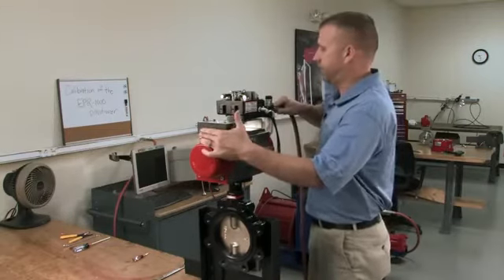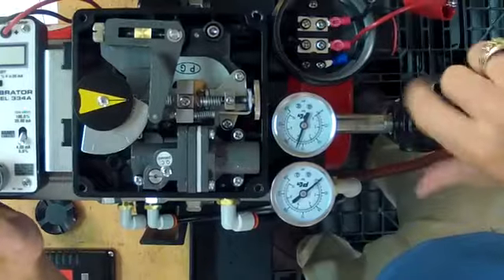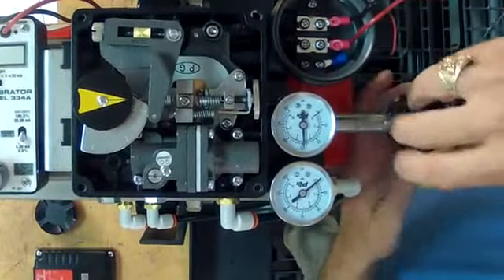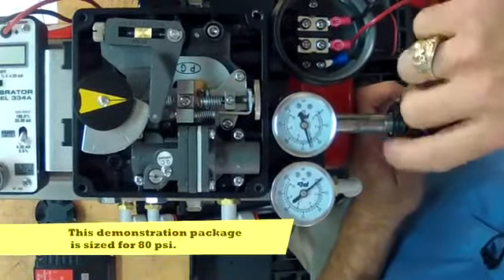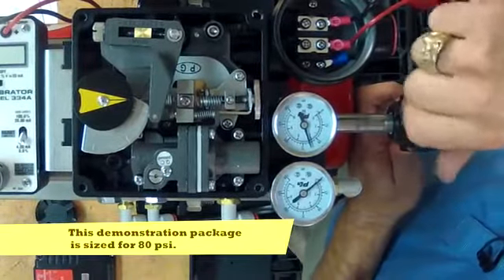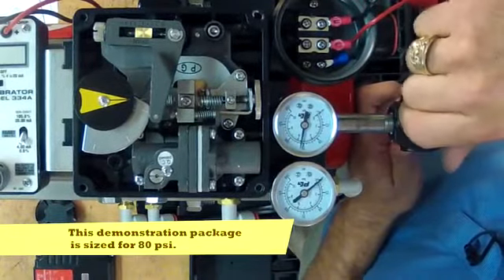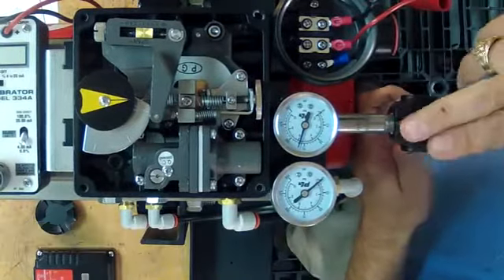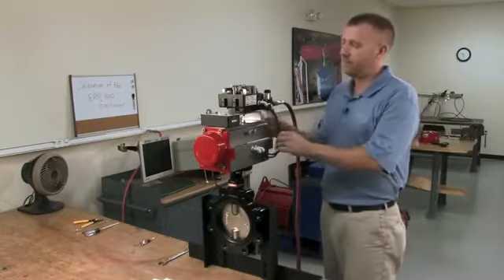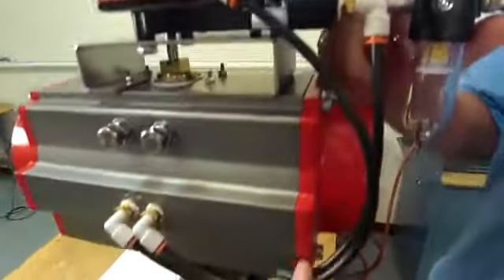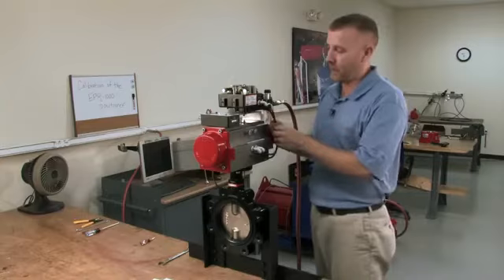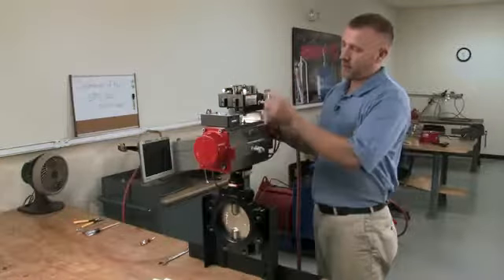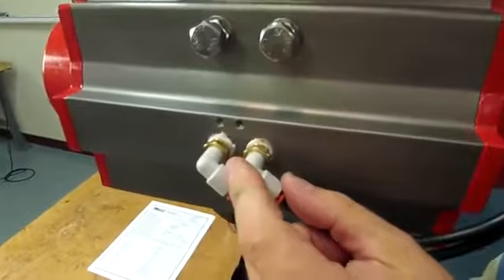Now I'm going to introduce the air on the actuator. We want to set our regulator to approximately 80 psi. And now we're going to start the basic calibration procedure. Just one more thing I'd like to explain is your tubing on your actuator. Your out 1 port goes to your counterclockwise drive port on your actuator. That would be for single acting. Like I said, we tube it up for double acting. So your out 1 goes to your counterclockwise, and your out 2 goes to your clockwise port.